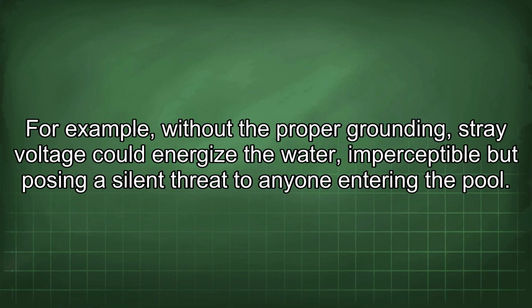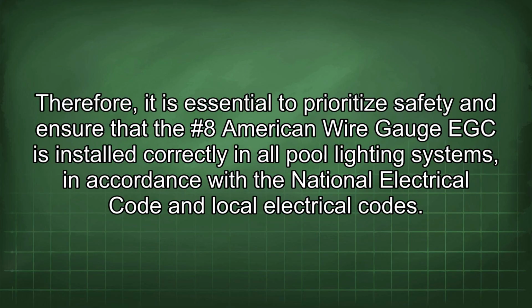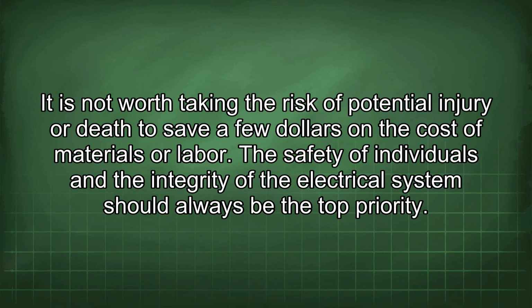For example, without the proper grounding, stray voltage could energize the water, imperceptible but posing a silent threat to anyone entering the pool. Therefore, it is essential to prioritize safety and ensure that the #8 American wire gauge EGC is installed correctly in all pool lighting systems in accordance with the National Electrical Code and local electrical codes. It is not worth taking the risk of potential injury or death to save a few dollars on the cost of materials or labor. The safety of individuals and the integrity of the electrical system should always be the top priority.